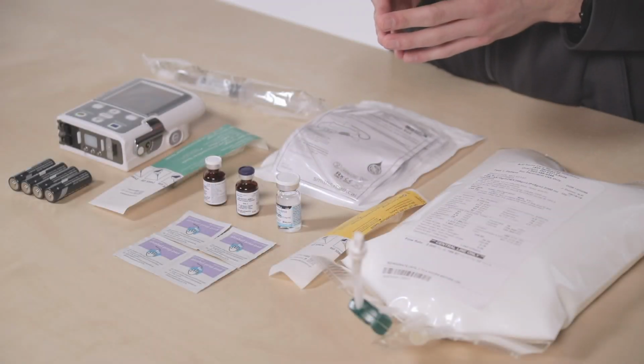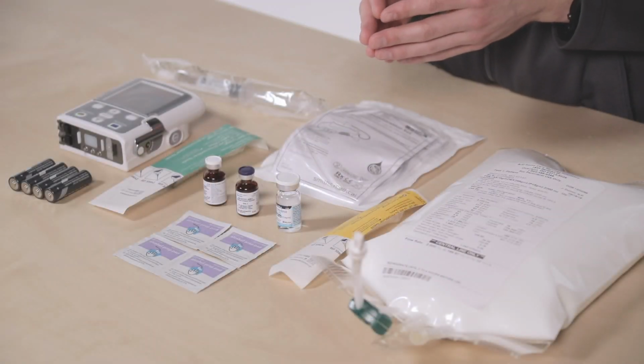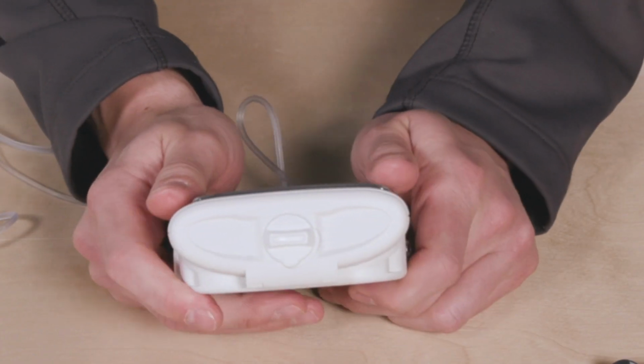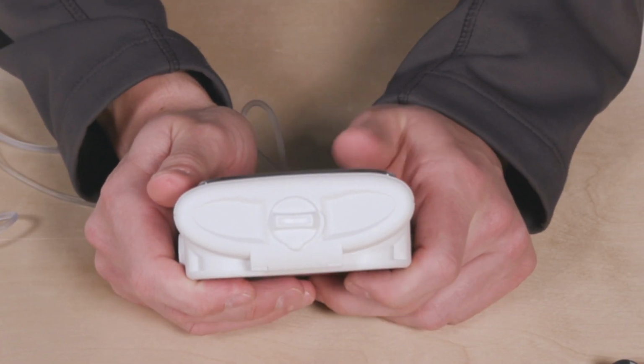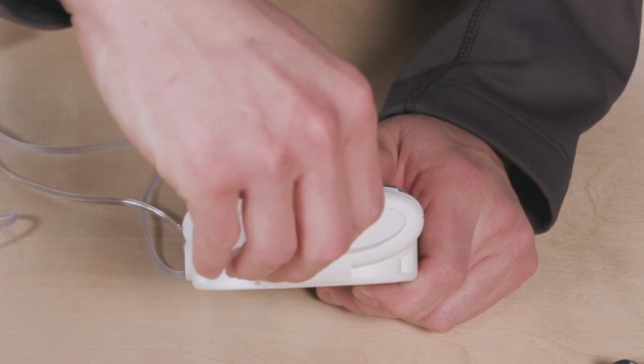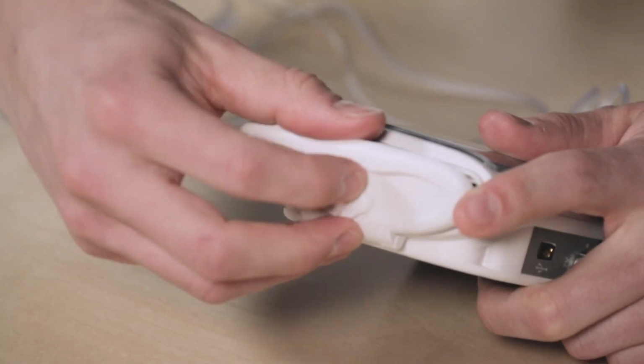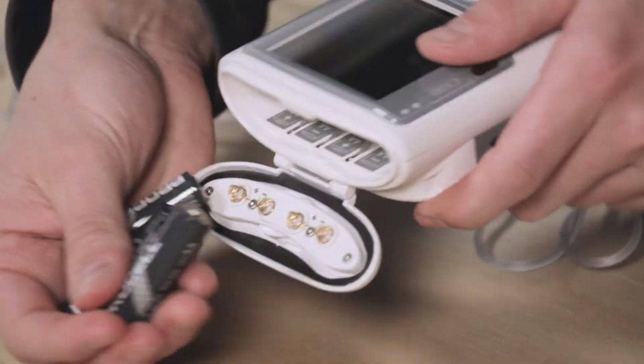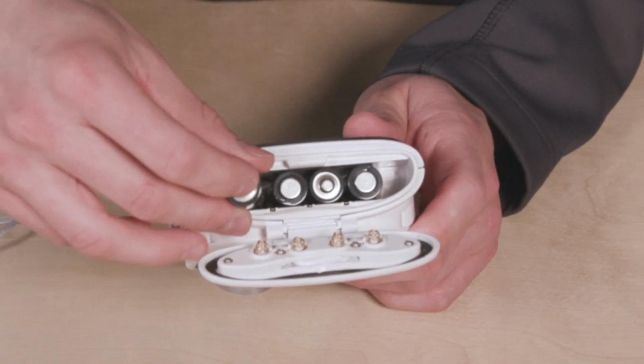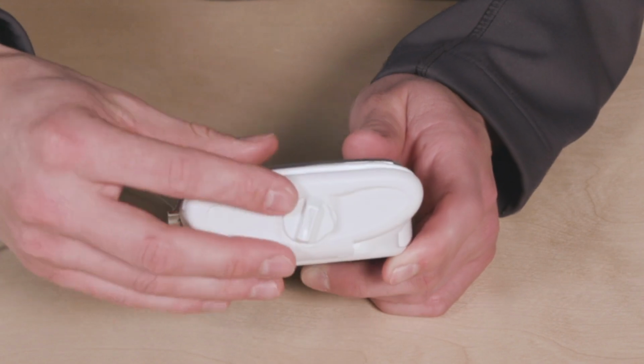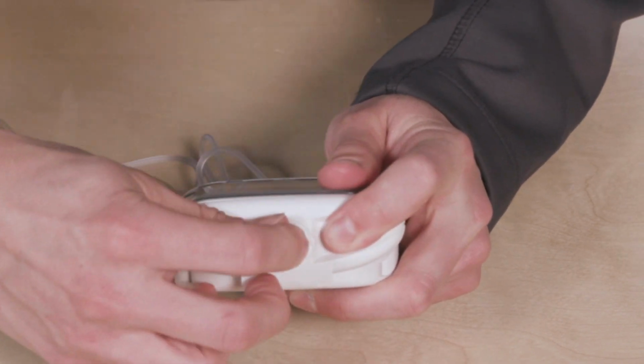Now that we have all supplies laid out on our work surface, we are ready to replace the batteries in our pump so that we start our infusion with a fresh set of batteries. Turn the white knob on the top of the pump. Remove and discard the old batteries. Replace with 4 new AA batteries.